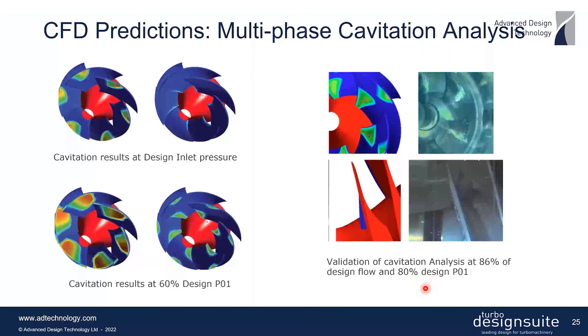There is very good correspondence between the regions of cavitation predicted by the multi-phase CFD and those observed in the experiments. There is also good agreement even for tip clearance induced cavitation between the CFD predictions and the test data.